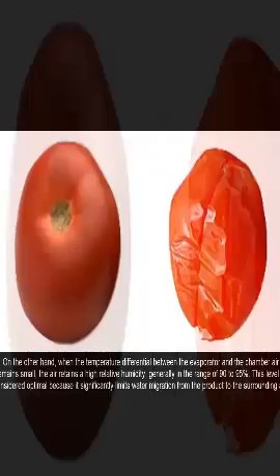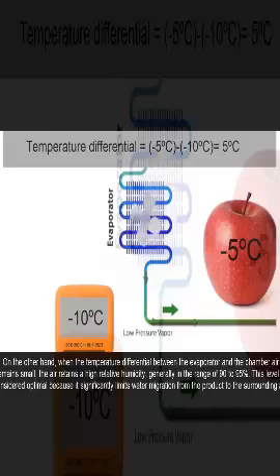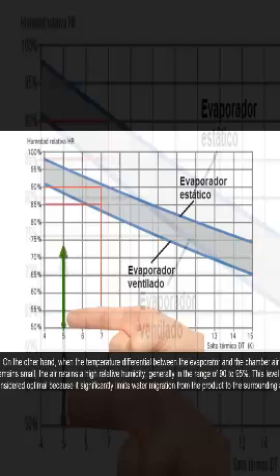On the other hand, when the temperature differential between the evaporator and the chamber air remains small, the air retains a high relative humidity, generally in the range of 90 to 95%. This level is considered optimal because it significantly limits water migration from the product to the surrounding air.